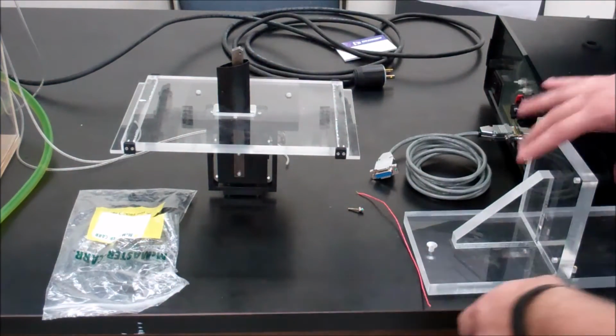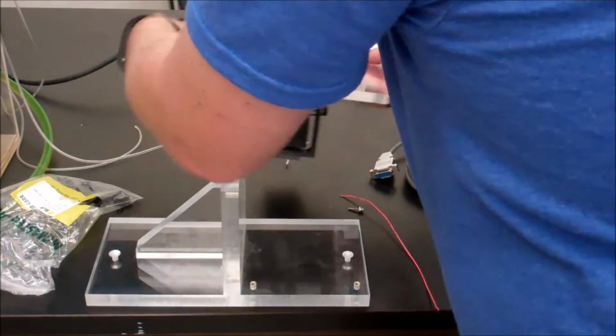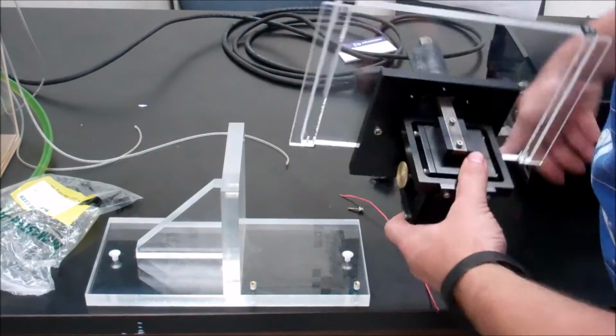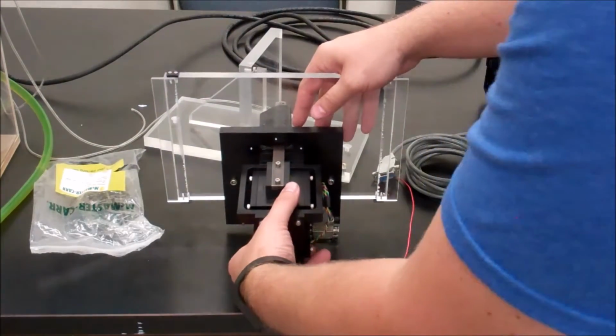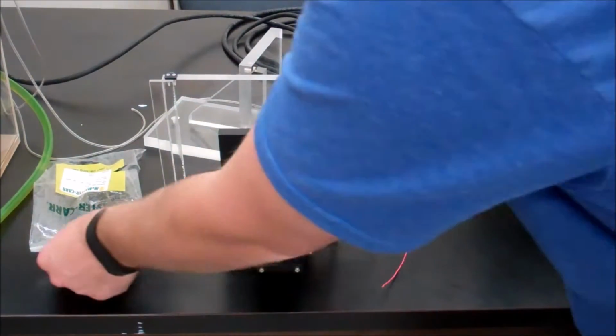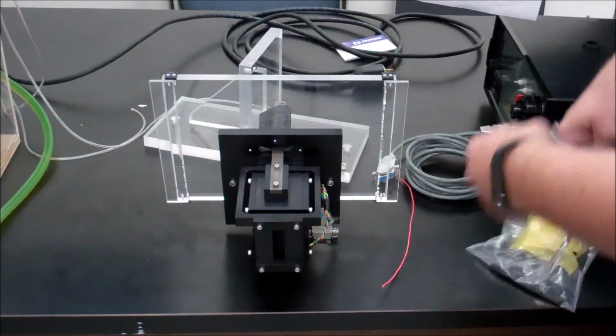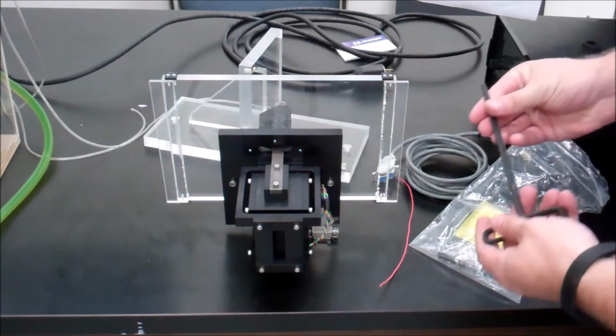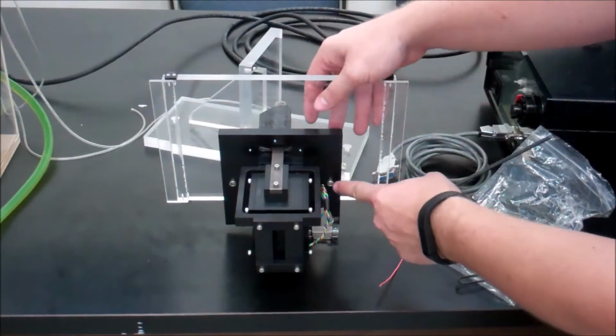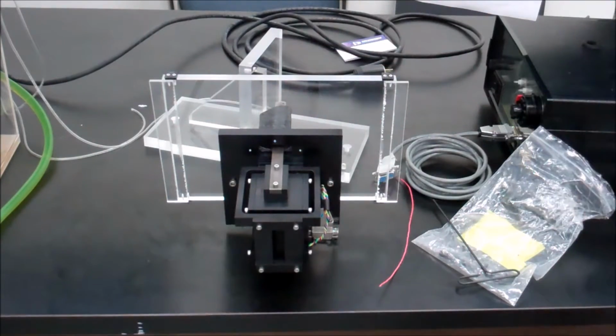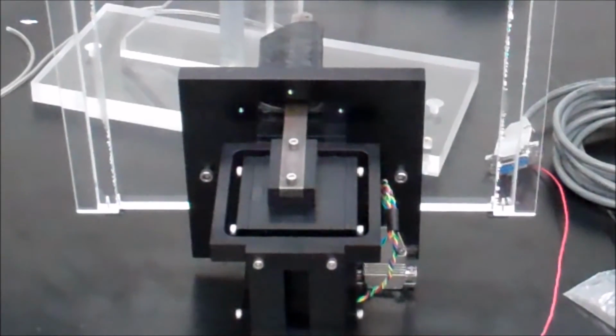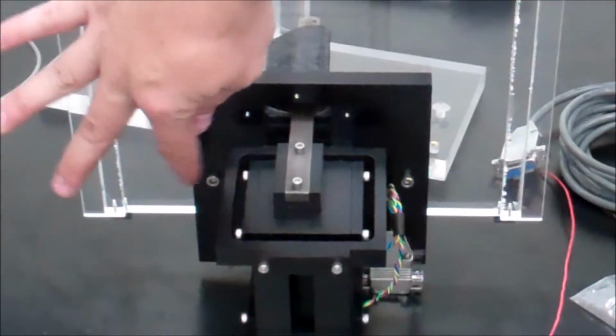Now what you need for calibration is this fixture unit. And what we have to do is turn the balance on its side, like so. You're going to take the bag of Allen wrenches and you're going to figure out which one fits into this silver screw hole there. So you see a silver screw right here and a silver screw right here.